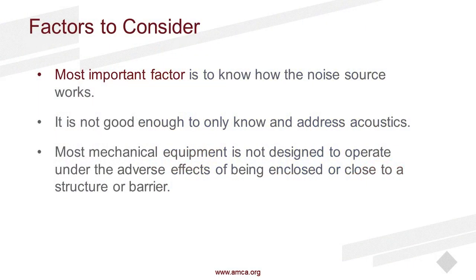Sometimes you might have to encroach upon the mechanical equipment more than expected, or more than the manufacturer would like, and we have to worry about warranties, work together, and prove how it's going to breathe properly. Then you look at maintenance access — what kind of access do you need? So the important thing, I can't stress it enough, is it's not only good to know acoustics, you've got to know how the equipment operates.